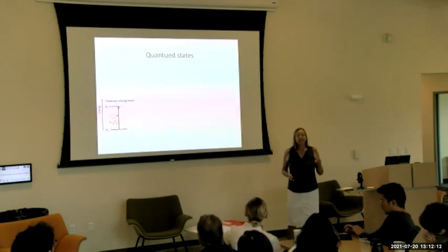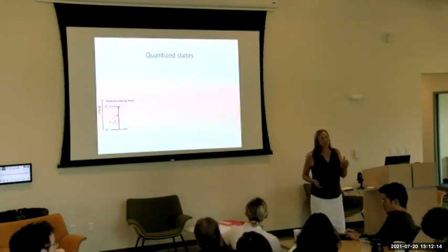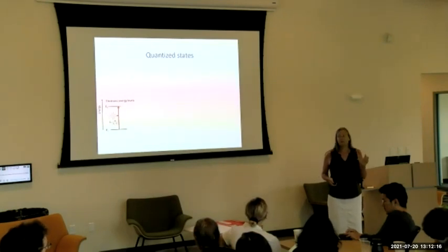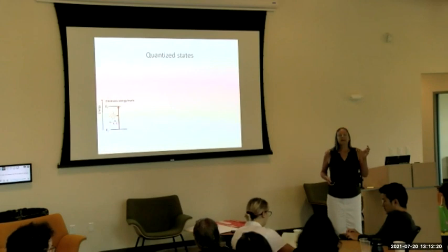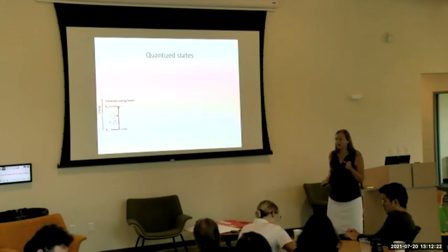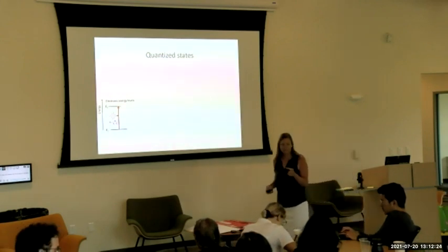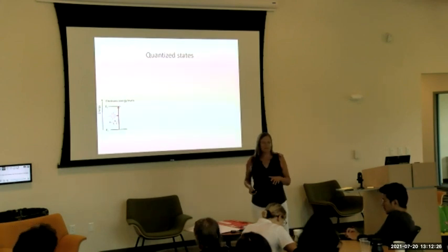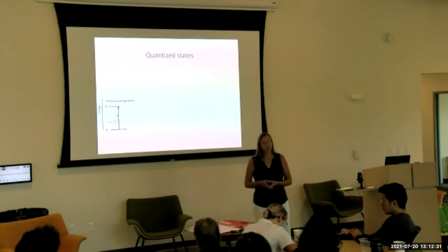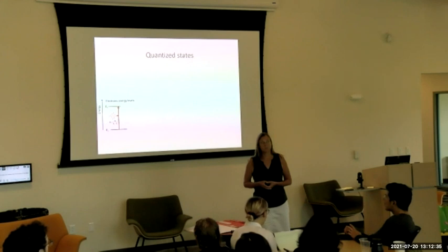Okay. And that becomes really important when we think about the fluorometers that we use in the ocean and how we are going to calibrate them. Because it turns out you can't calibrate them to a pure solution of chlorophyll because they excite at a wavelength that chlorophyll does not absorb.